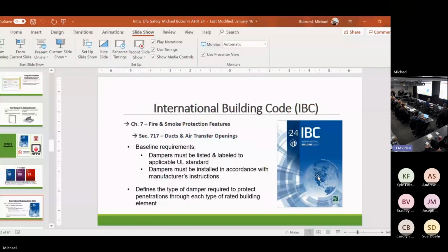This is going to be your containment dampers. Chapter 7 is open and closed dampers. All right, I'll tell you what standards they must be listed and labeled to. And this is the important part when we talk radiation dampers. Again, I'll say it again. The building code cannot say dampers must be UL listed. You're not allowed to do that in the building code. It creates a competition problem. I forgot what that word is. Building code only says dampers must be listed and labeled to the applicable UL standard. That comes into play with radiation dampers every day. Talk about that later or offline if we have to.